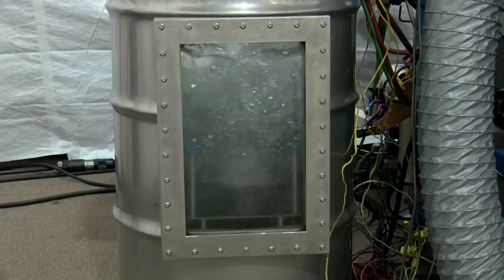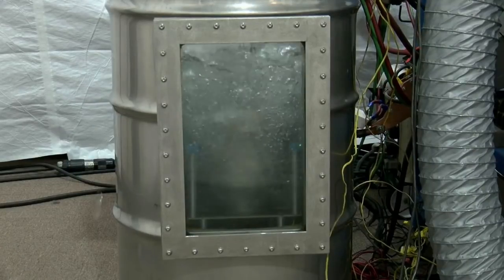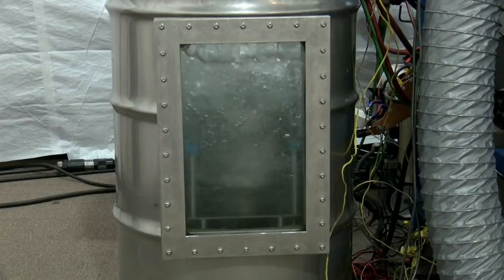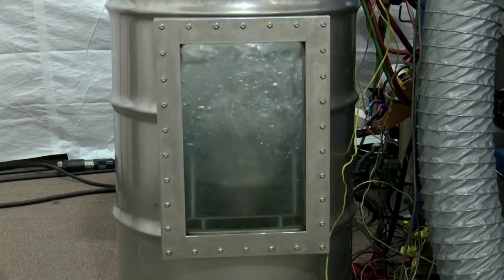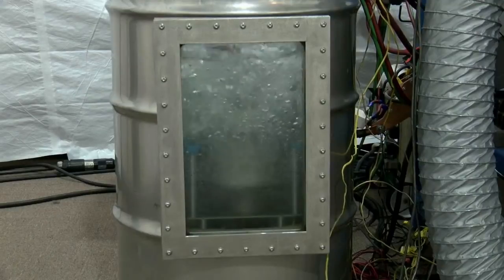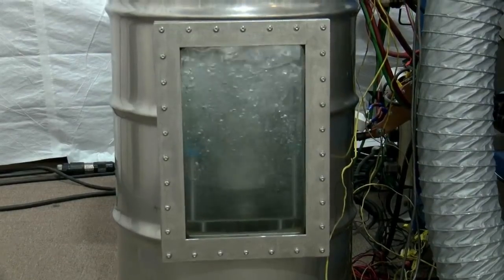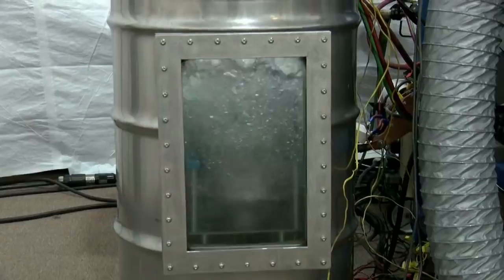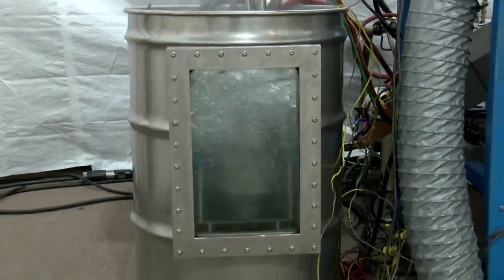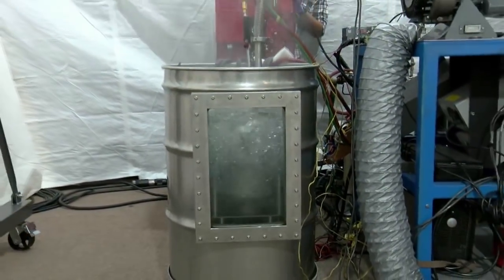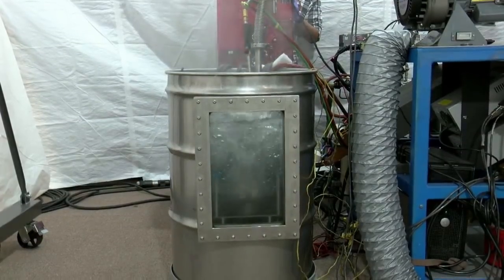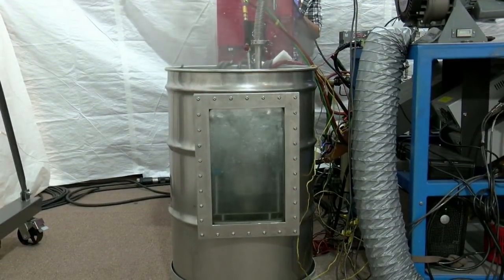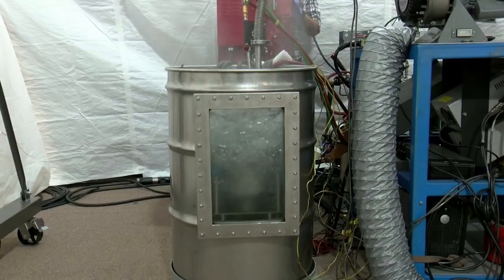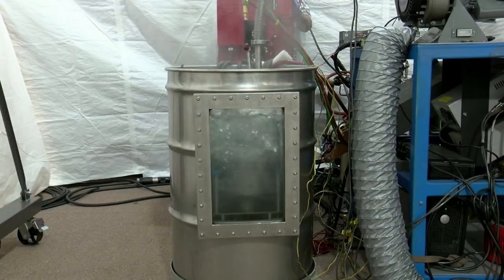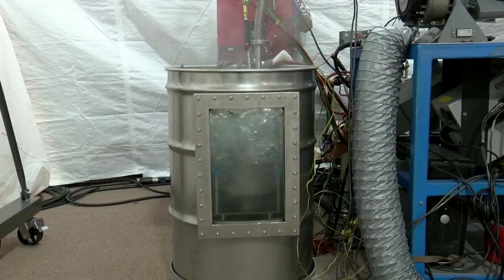What we're going to do is turn that off, because we don't want to overload the data center here with a thermal load. But you can see it's very, very profuse boiling as they brought it up to power. So about 150,000 watts, and we've run validated systems, as I said, at 275,000 watts. So I'll just wait a second. So you can see that a little longer. Okay, we'll cut back to me.